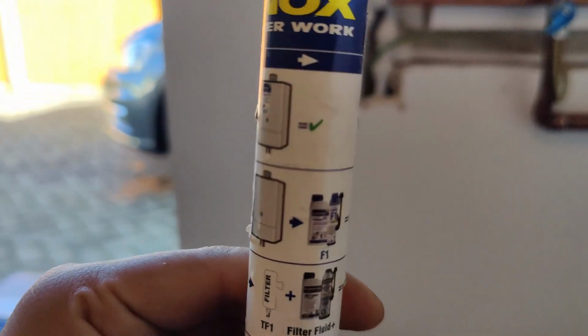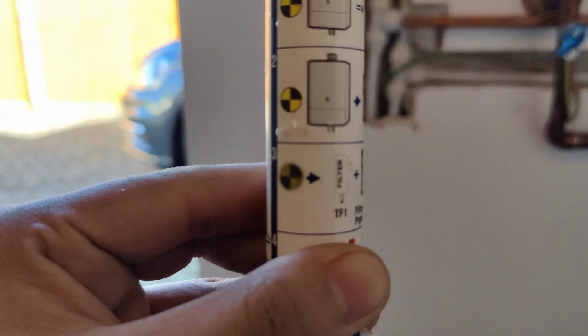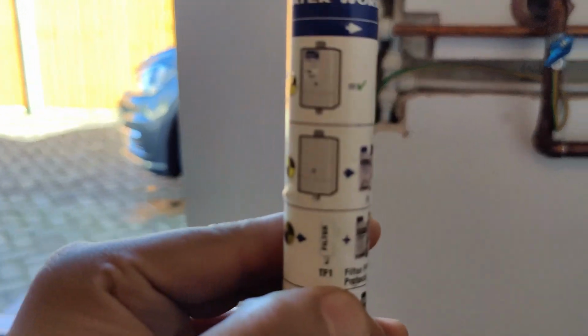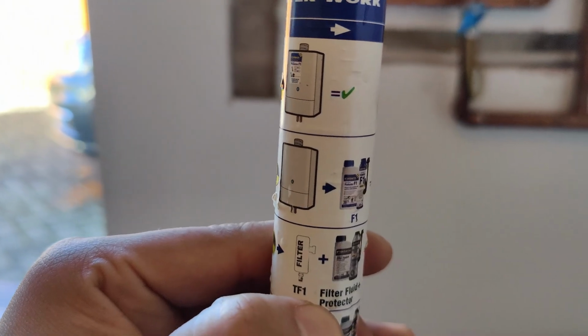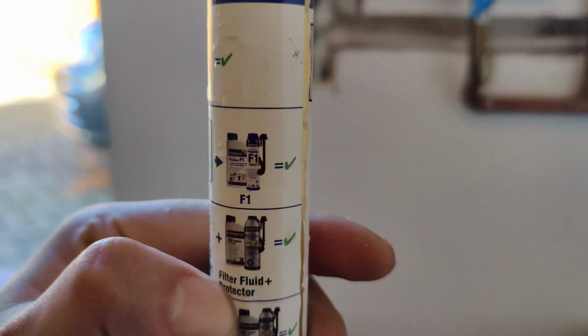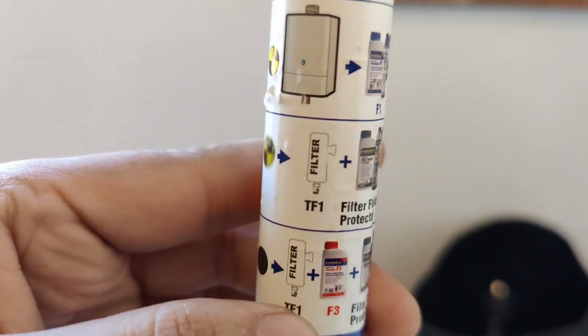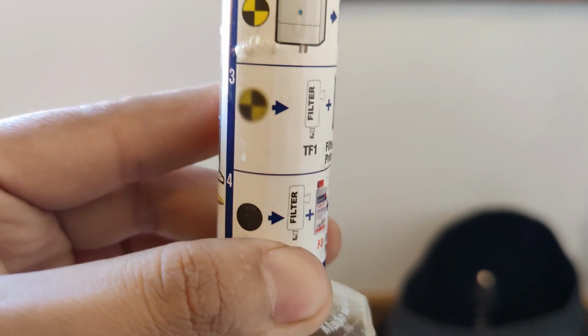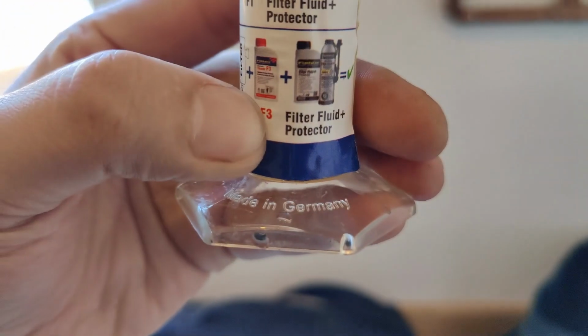Number one. Number two, if it requires the protector, to top up. Number three, if it was murky, then they would recommend a filter. Now this installation already has a filter and the protector. And if it was really mucky, so that you couldn't see down it and couldn't see that sign right at the bottom, then it would require a filter, a cleaner, possibly a power flush, and then a protector.